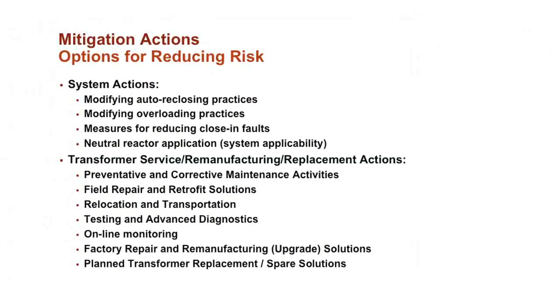Okay. So now, typical things that can be done to mitigate the risk of failure. One thing is doing diagnostic testing, something more advanced than just ratio and resistance, and I'll show that. Normally that's a frequency response analysis or dielectric frequency response. You can do internal upgrades on a transformer. Say a design study has shown certain dielectric weaknesses in the transformers. In some cases, you can go inside the transformer and make modifications to take away those dielectric risks. Bushing replacement, as I said, can be a very good way to reduce risk of failure.